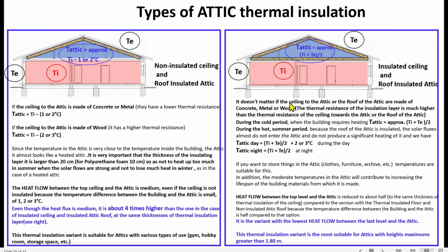Insulated ceiling and roof insulated attic. It doesn't matter if the ceiling of the attic or the roof of the attic are made of concrete, metal, or wood. The thermal resistance of the insulation layer is much higher than the thermal resistance of the ceiling towards the attic or of the roof of the attic. During the cold period, when the building requires heating, T attic is approximately (T interior plus T exterior) divided by 2.